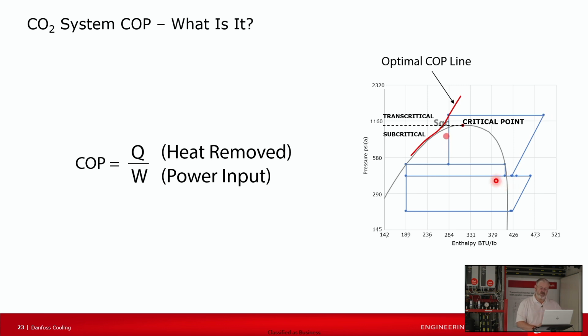And it works to keep the temperature exiting the gas cooler on this line, because it knows that as long as that is happening, we're using just the amount of energy necessary to do this work. And that's all you want. There's really not a way to use less, per se, but we want to use just the energy required. So the high pressure valve, while it does serve the purpose of giving us liquid in warm ambient, really cares most about energy usage by your compressors and maintaining specific conditions in the gas cooler.